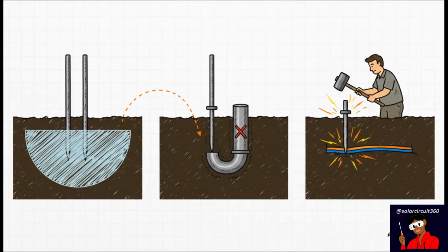But man, it is incredibly easy to get this wrong. The absolute most dangerous mistake is improper probe spacing, which creates overlapping resistance zones. If you put the probes too close together, the areas of soil they're measuring literally overlap, and that gives you a dangerously false low reading. Your tester might be telling you your ground is perfect, while in reality, it's a massive hazard.